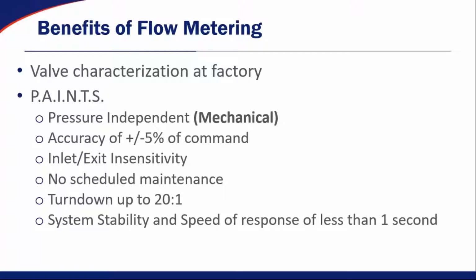We guarantee accuracy of plus or minus 5% to command, and that's across the entire pressure range of the Phoenix control valve, as well as the entire flow range of the Phoenix control valve. We have inlet and exit insensitivity, which means it doesn't matter what elbows you have in the ductwork in your building, you can install a Phoenix control in the most challenging environments and still get the same accuracy, the same controllability out of that device.